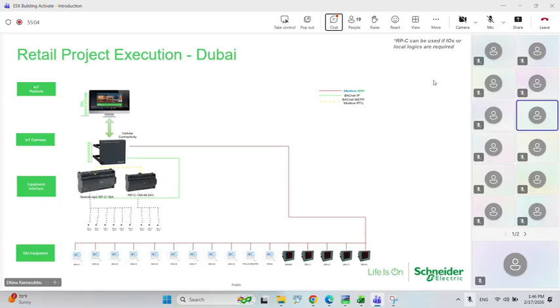They had manual switches, through which the local store team controlled those lights. Additionally, they had basic Honeywell thermostats controlling the AHUs. These AHUs are high energy consuming equipment, around 5 kilowatts. So what we did is simple automation.